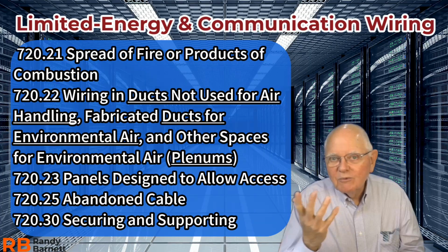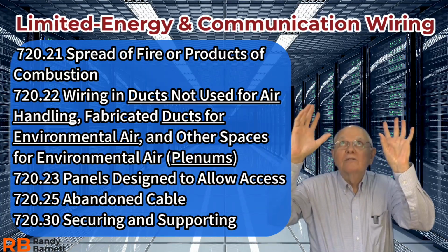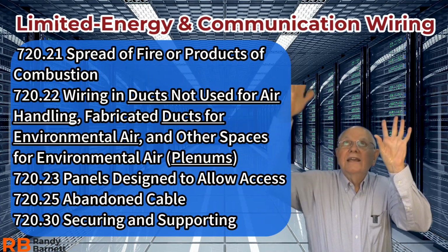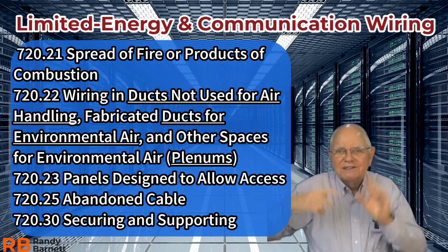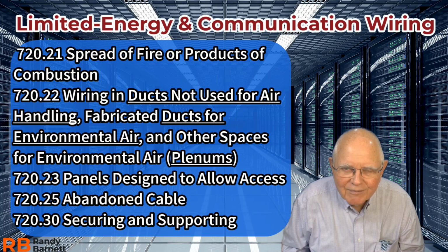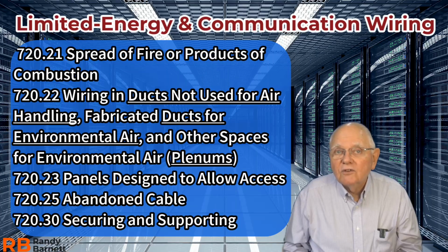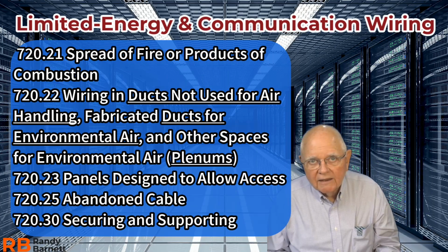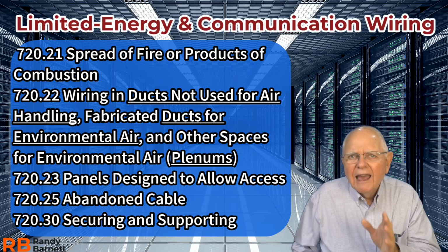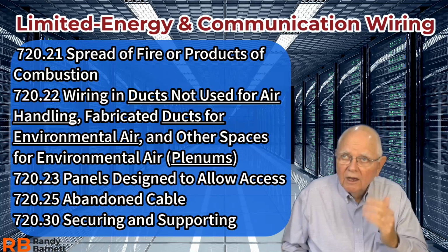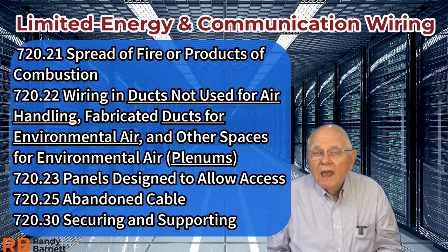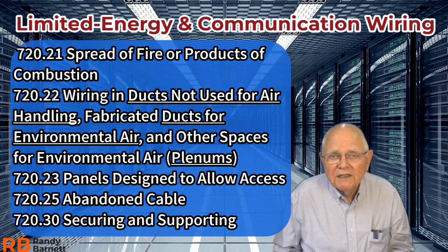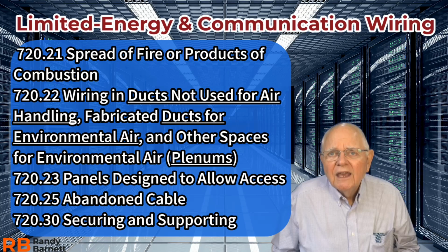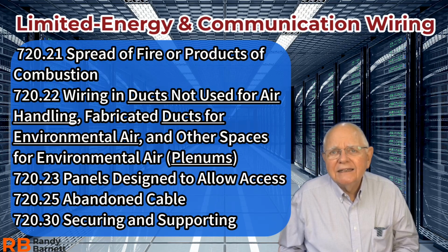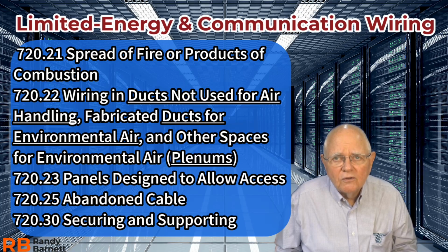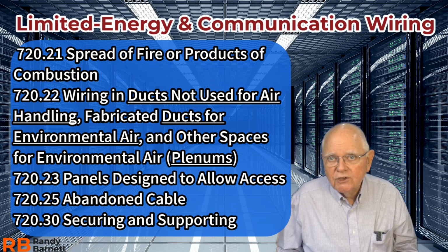Okay. I remember, one time, I pushed up a ceiling tile, and it was like an avalanche of all of these cables that came down, falling on top of me. So that's not allowed. 720.23 talks about that. So it's going to tell us elsewhere how we have to support these cables above that suspended ceiling. Abandoned cables, of course, this has been in the code for some time. Accessible portions of abandoned cables shall be removed or tagged for future use.